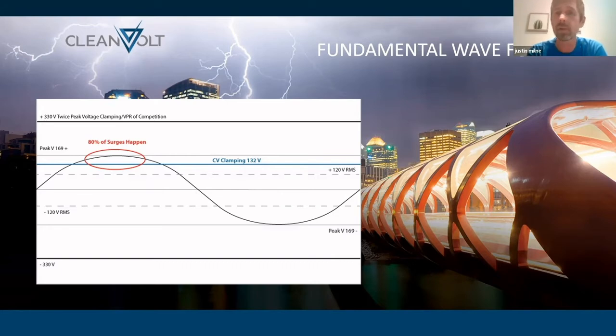The average VPR we find on most 120 volt levels is anywhere from 400 volts up to 900 volts. With CleanVolt, we start to react at 132 volts. This does not mean that we're constantly clamping, because we are geared to see a 60 or 50 hertz signal, but once that signal increases in nature, we start to conduct and attract that energy surge to our device so that it can't affect any of the connected components or create any type of residual effect that's going to have an impact on your efficiency.